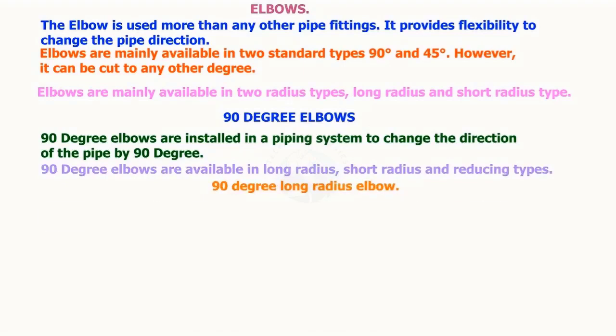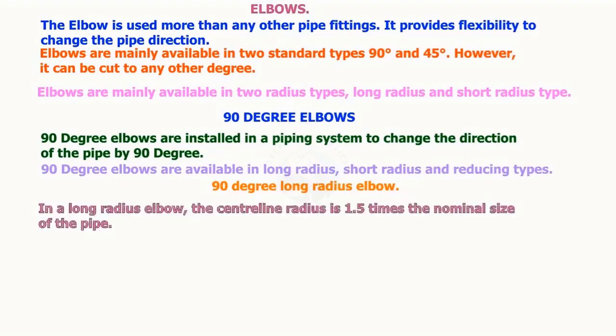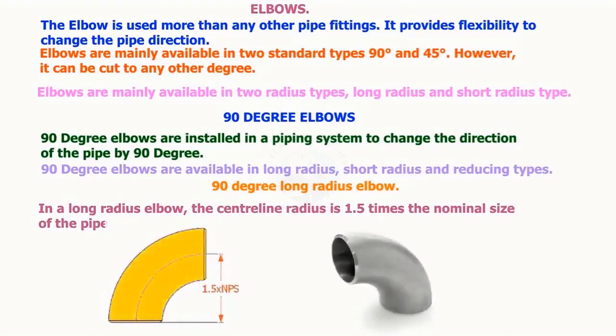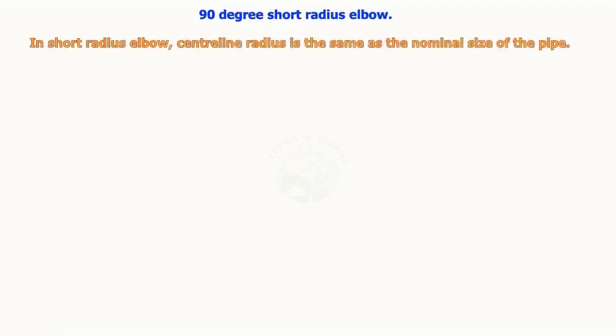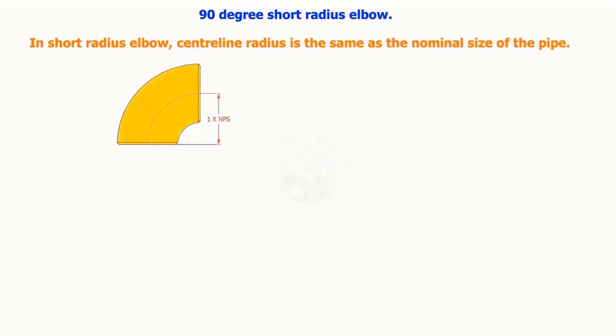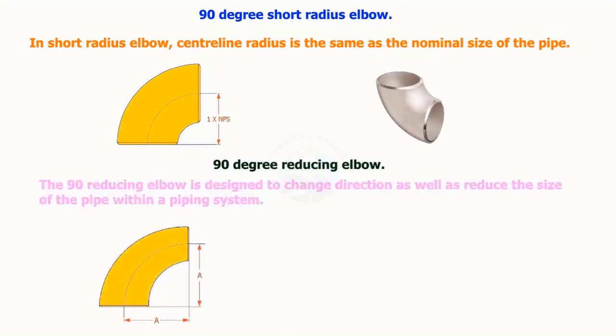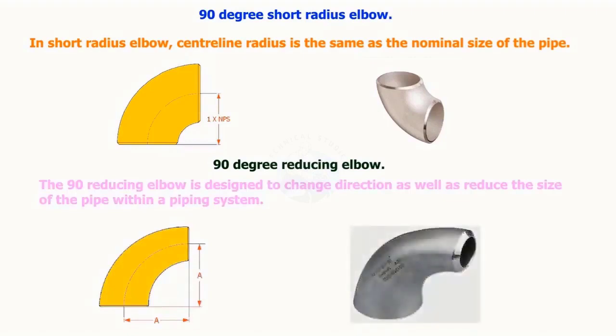In a long radius elbow, the centerline radius is 1.5 times the nominal size of the pipe. The 90-degree reducing elbow is designed to change direction as well as reduce the size of the pipe within a piping system.